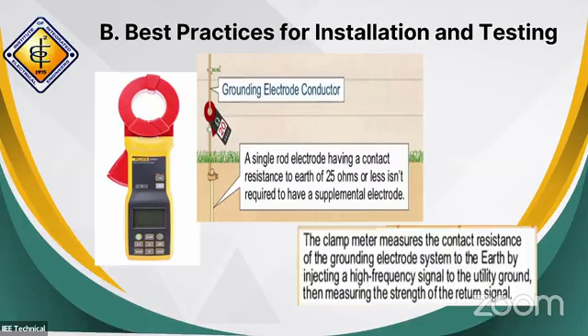Yan, tapos ang kagandahan nito, kanina binanggit yung residual. There's a specific model for testing material, testing equipment that can measure also residual current going to the ground rod, not only for resistivity alone. Kaya ma-check mo talaga eh saan nanggagaling yung residual current. From there kailangan may corrective measures, tanggalin yung pinanggagalingan or i-correct, ayusin.